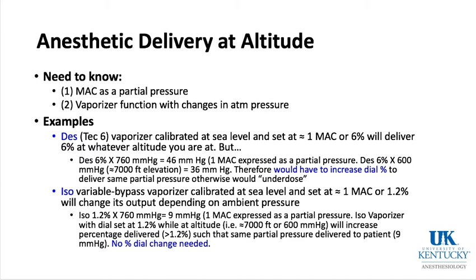You'd actually be delivering a higher percent than 1.2%, but now instead of 1.2% times 760, it would be maybe 1.4 or 1.5% or something like that times 600, and you end up with a very close same delivery of millimeters of mercury, and no change is needed to that isoflurane variable bypass vaporizer. It self-calibrates basically, or self-calibrates partial pressure delivery.